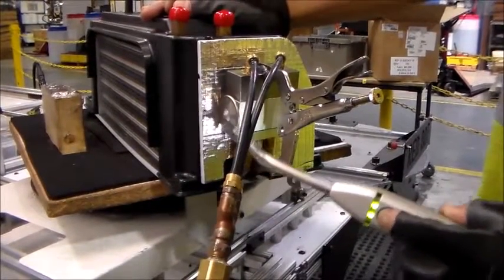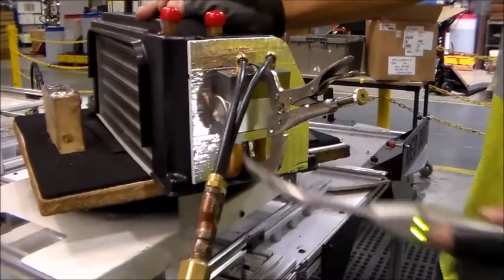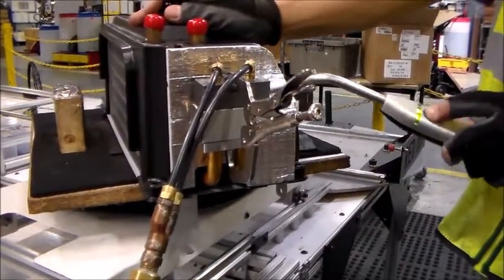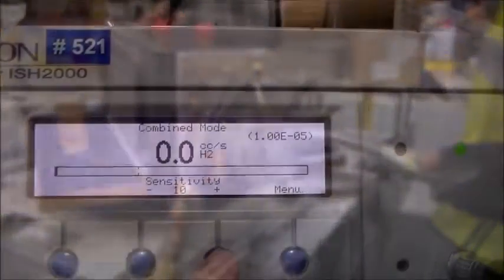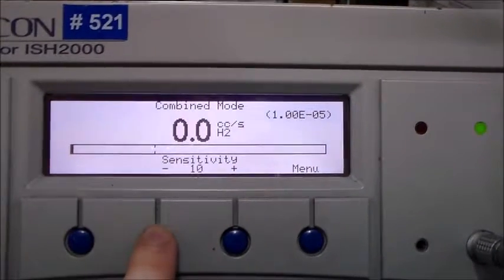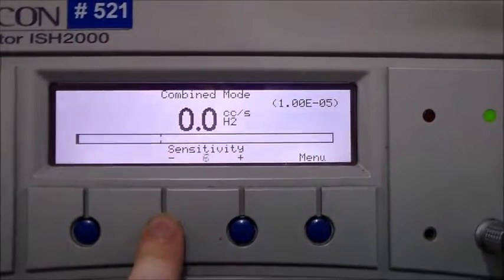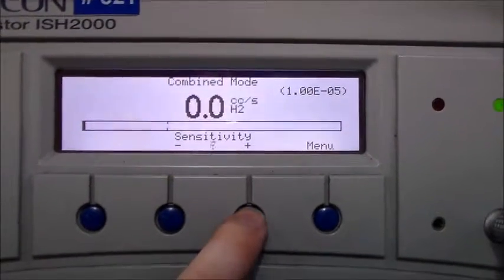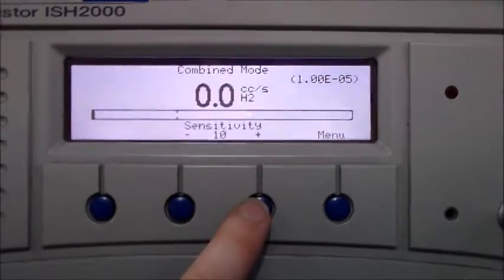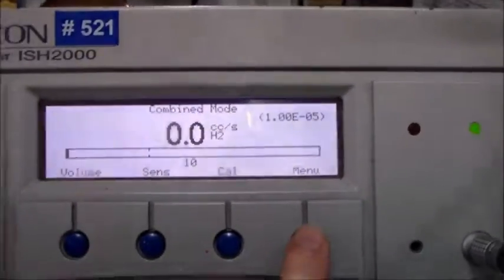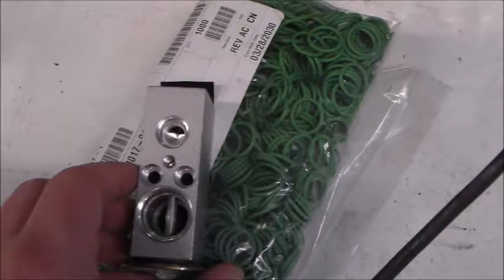If the part fails the test again, try to locate the leak using the probe. The alarm will get louder and the bar will increase when you get closer to the location of the leak. Adjust the sensitivity on the machine depending on how close you want to locate the leak. Decrease the sensitivity so you can get closer to where the leak is originating from, but return it back to 10 for normal testing. Check all O-rings on the expansion valve and replace them if damaged and retest.